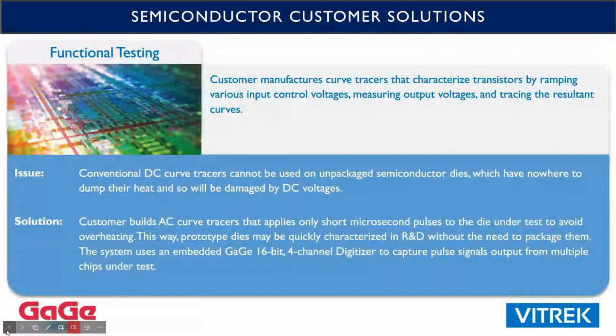So I'll continue. The curve tracer is a device that normally applies DC voltages to a transistor chip and then measures currents. And typically there's a couple of control voltages and one measured current. So you may have seen one of these analog devices way back in the 60s or even earlier. It looks like an oscilloscope, but it produces these elaborate traced curves that characterize the transistor.